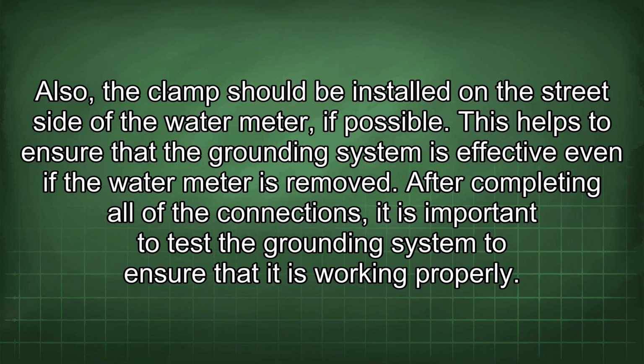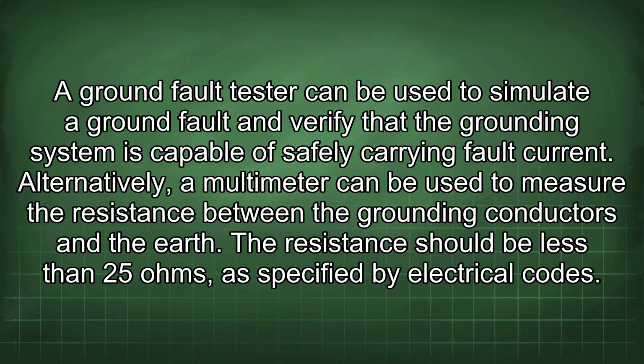After completing all of the connections, it is important to test the grounding system to ensure that it is working properly. A ground fault tester can be used to simulate a ground fault and verify that the grounding system is capable of safely carrying fault current. Alternatively, a multimeter can be used to measure the resistance between the grounding conductors and the earth. The resistance should be less than 25 ohms, as specified by electrical codes.